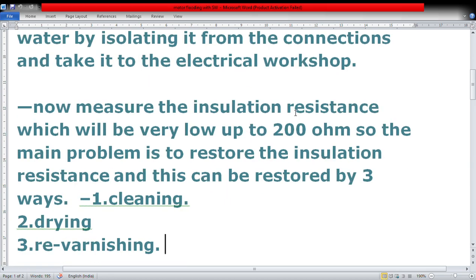Measure the insulation resistance, which will be very low, around 200 ohm. The main problem is to restore the insulation resistance, which can cause short circuits or motor burning. This can be restored by three ways: cleaning, drying, and re-varnishing.